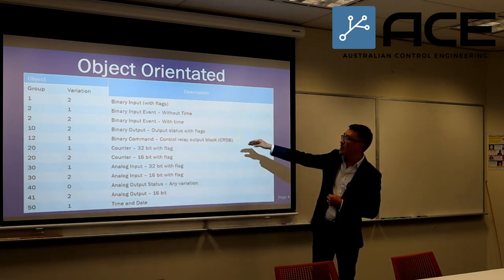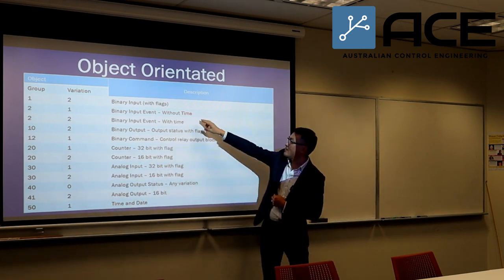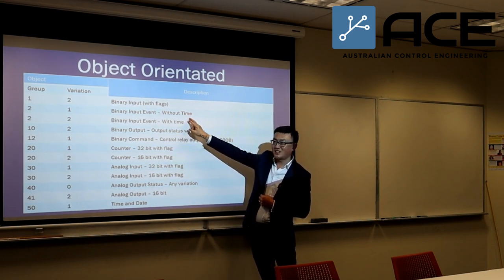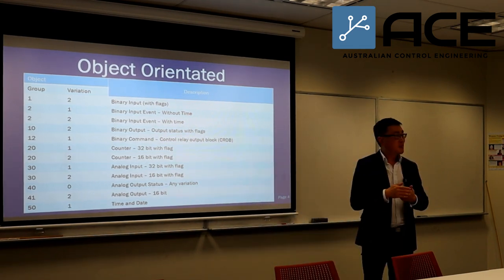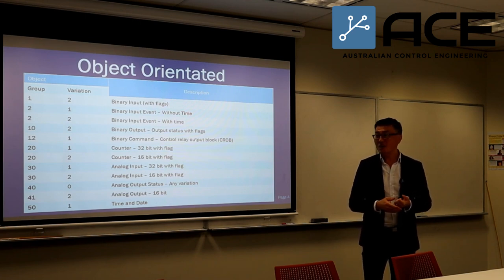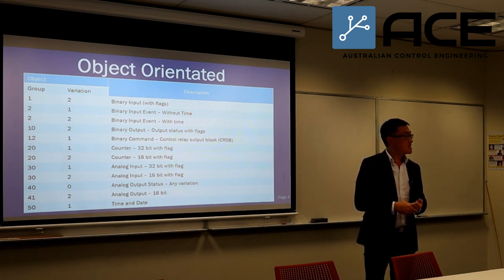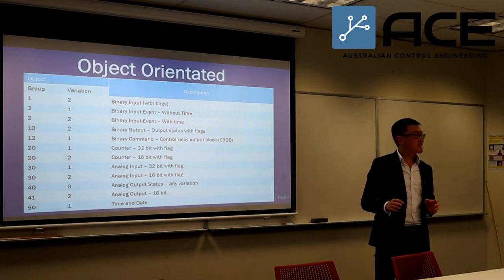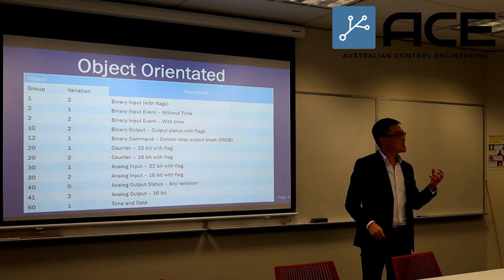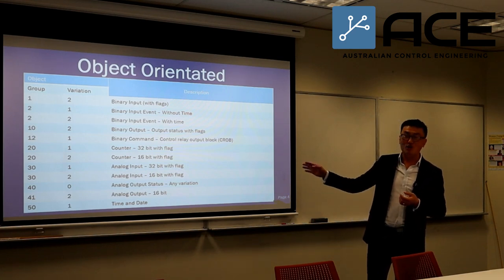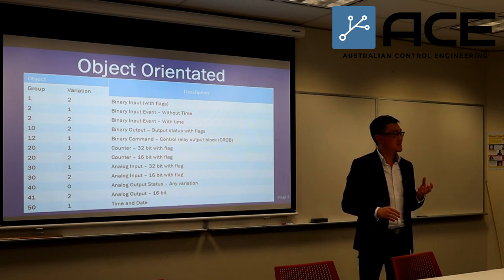You might ask why the time is highlighted in red. That's because Modbus, EtherNet/IP, Profinet, Profibus, and DeviceNet — all of those protocols don't have time. I know this sounds weird; how can you communicate without time? But DNP3 communicates with a timestamp on it.